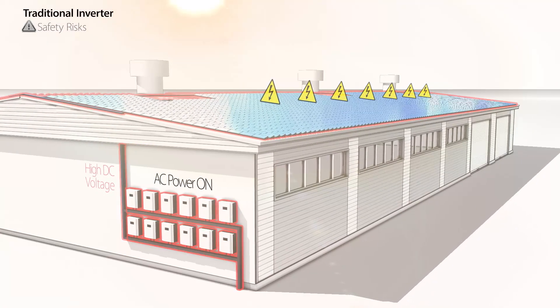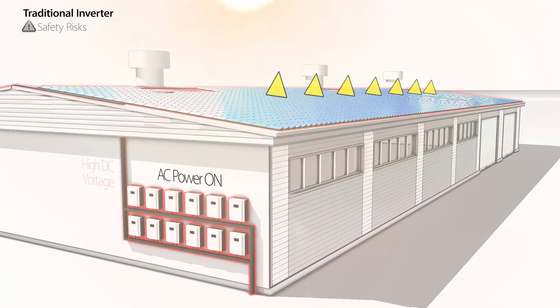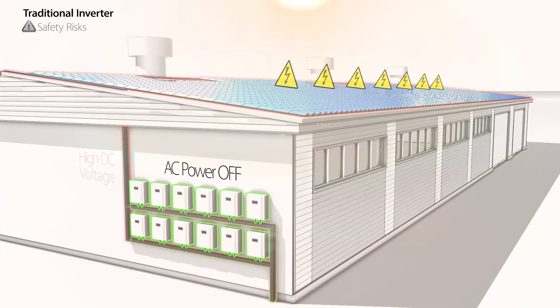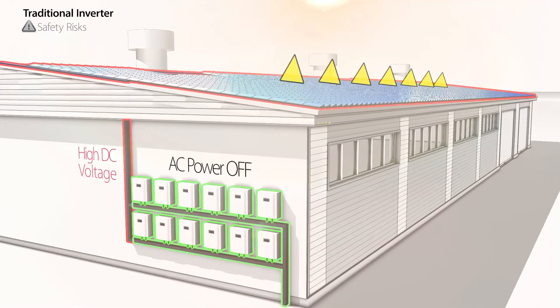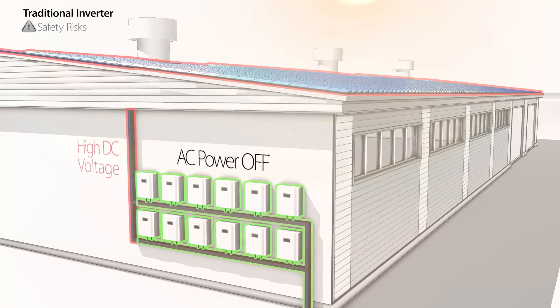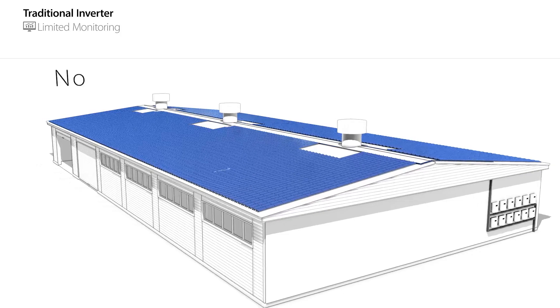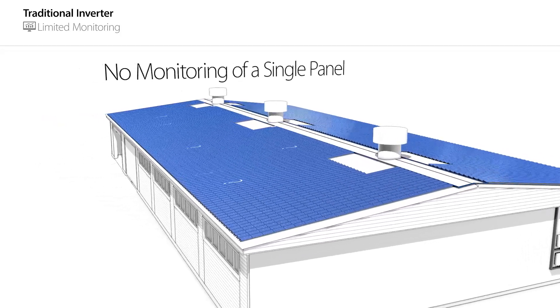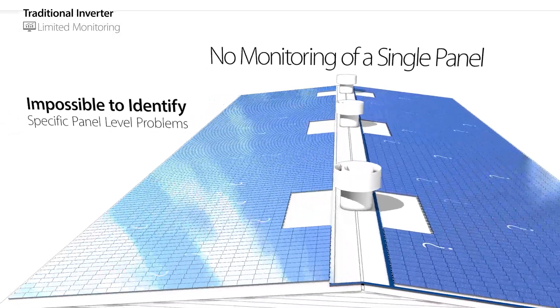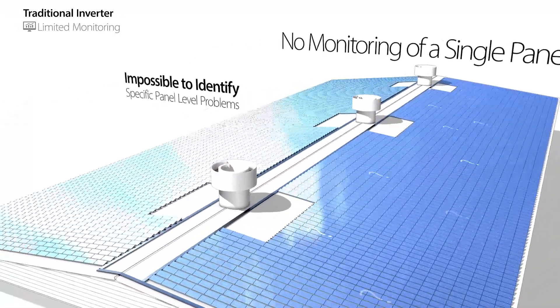A third drawback is safety issues. The DC cables that connect the panels to a string carry high voltage as long as the sun is shining. The traditional inverter cannot shut down the DC voltage of the panels, and therefore there are serious associated risks for installers and firefighters. And lastly, a traditional system cannot track power output, temperature, or any other parameter of a single panel, making it impossible to identify specific panel-level problems remotely.